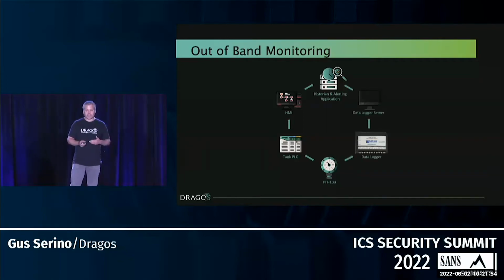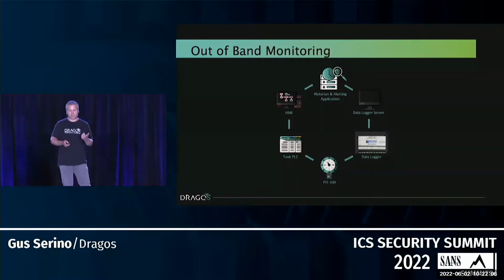On the other side, in that same 4 to 20 milliamp loop, we send that pressure signal to a data logger, which goes up on its own telemetry to a data logger server, and then into the historian. From there, we can compare those two signals with the historian and figure out if the pressure indication through the traditional SCADA route is equal to the same one coming over that alternate path, and figure out if there's a discrepancy there.